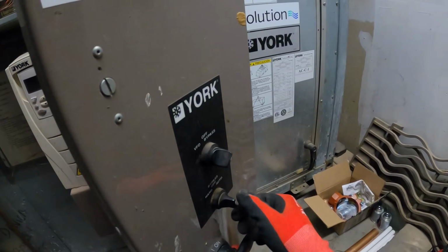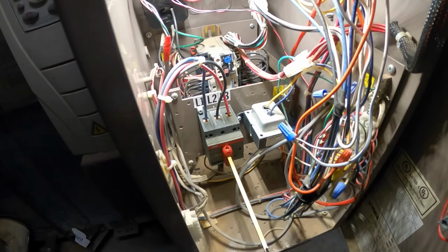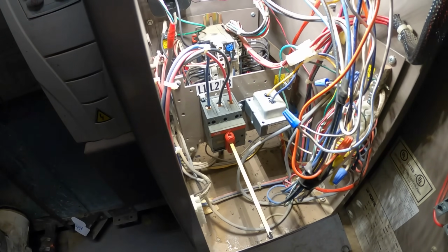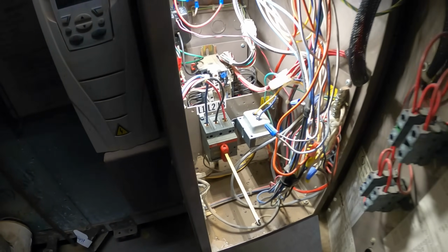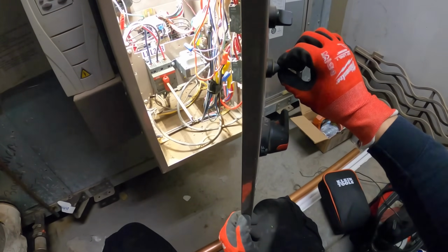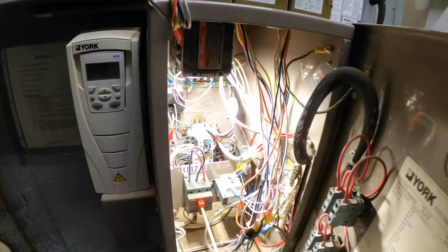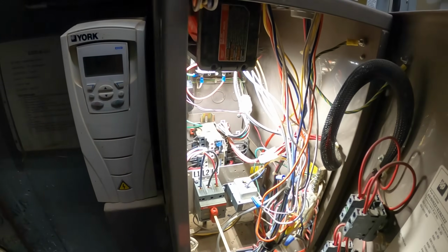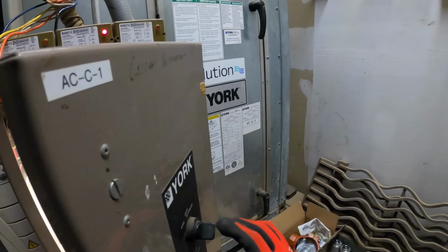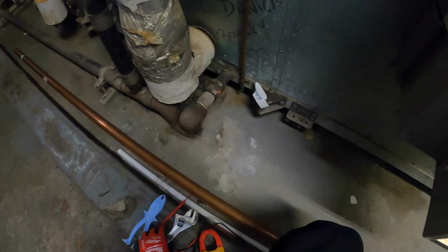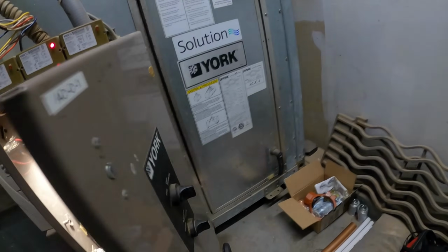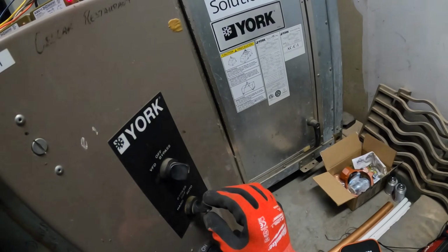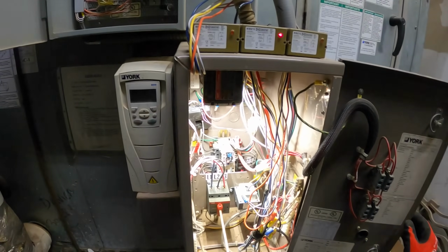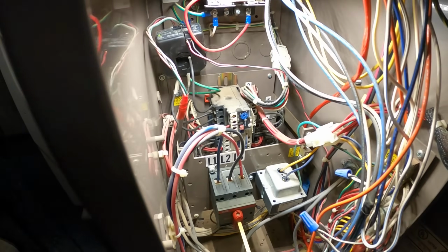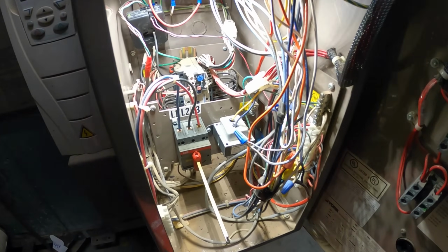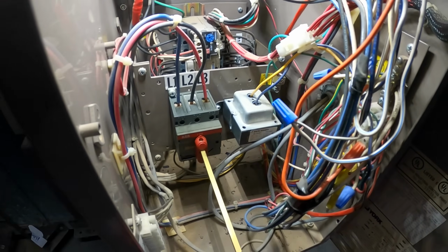All right, bypassed VFD, and let's put it on hand. Does it plunge in? No. Nothing happens on hand. Who's sending power for this control circuit? Let's leave it on bypass and hand. That fan should come right on. But if those contacts don't plunge in, the motor's never gonna get power. I'm thinking this could be a control issue.